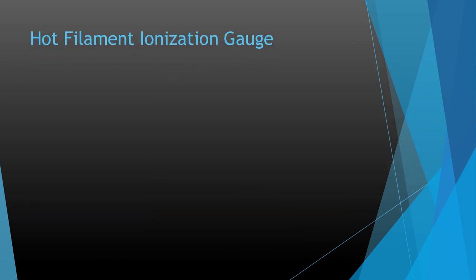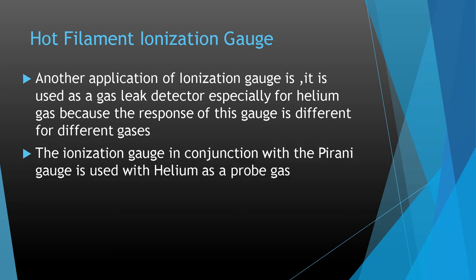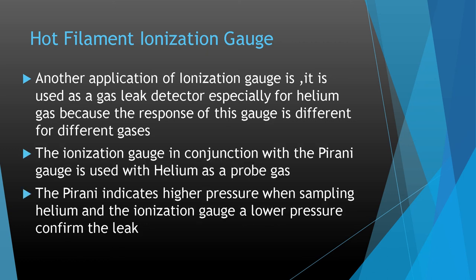Another application of the hot filament ionization gauge is its use as a gas leak detector, especially for helium gas, because the response of this gauge differs for different gases. The ionization gauge in conjunction with the Pirani gauge is used with helium as a probe gas — the Pirani gauge indicates higher pressure when sampling helium, while the ionization gauge showing a lower pressure confirms the leak.